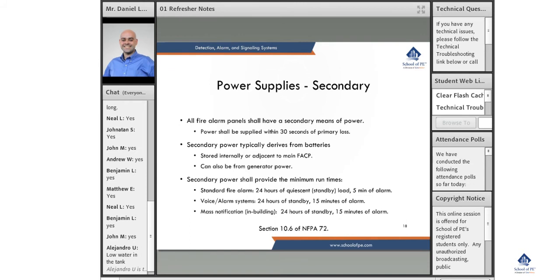The code actually does have a note that the battery calculations must include a minimum 20% safety margin above the calculated amp hour capacity required. So whatever is calculated, the code requires you to put in a safety margin. That is section 10.6.7.2.